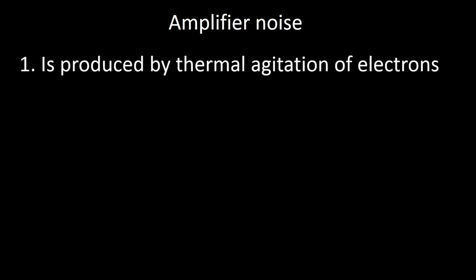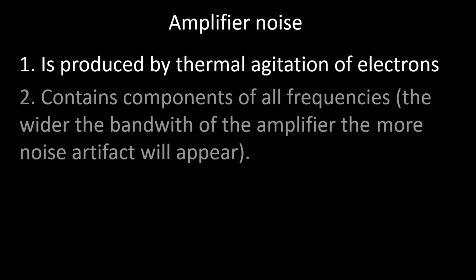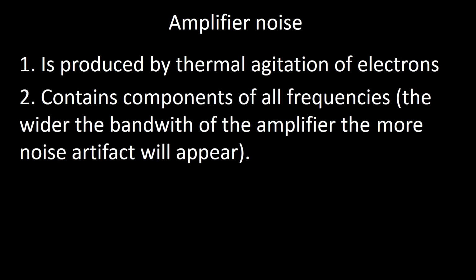In the next few seconds, I will mention some important points regarding amplifier noise. Amplifier noise is produced by thermal agitation of electrons within the amplifiers. Amplifier noise contains components of all frequencies. The wider the bandwidth of the amplifier, the more noise artifact it will produce. Thus, in addition to 60 Hz artifact, noise amplifier will inject into the tracing artifact of much faster rhythms.